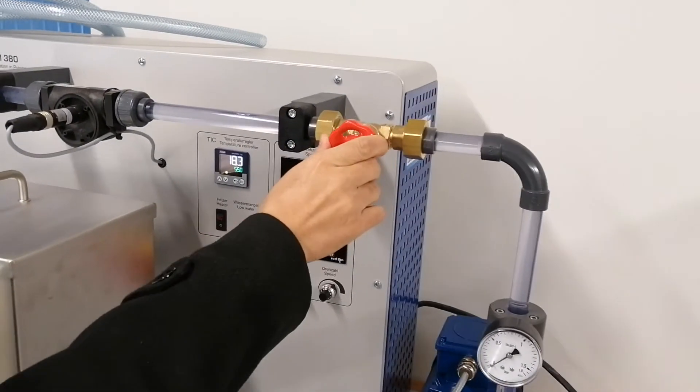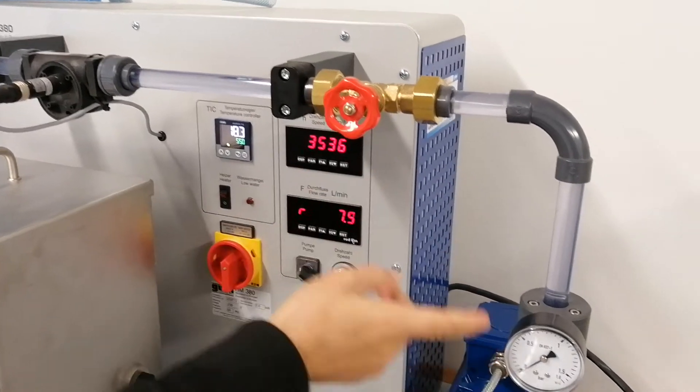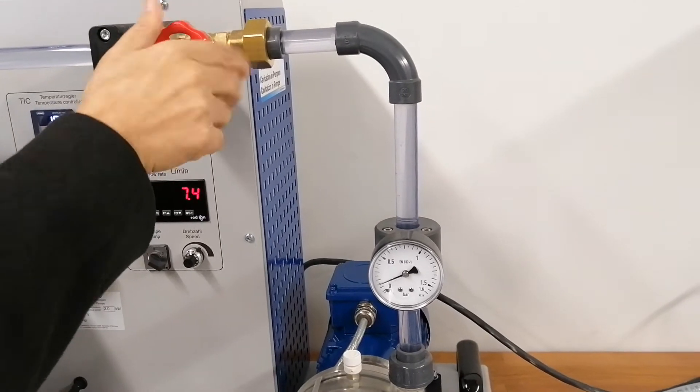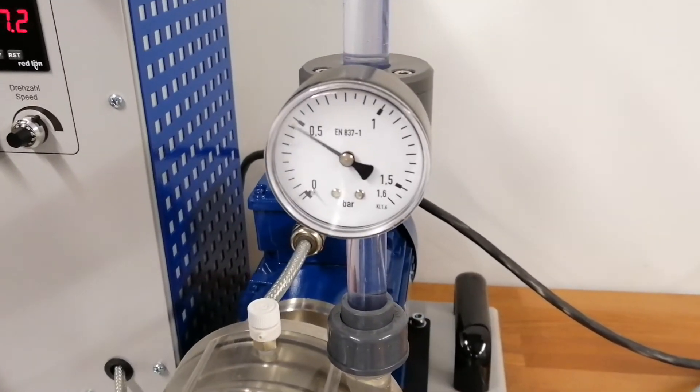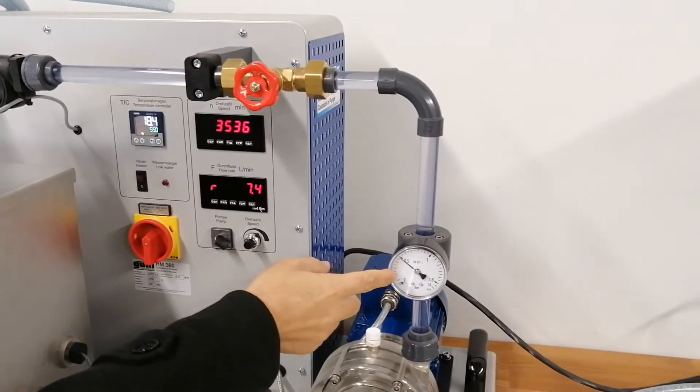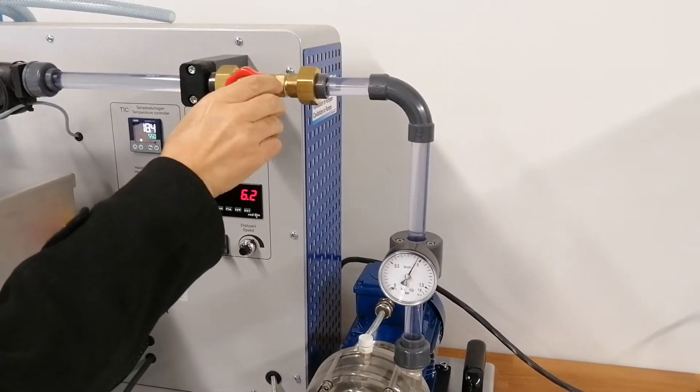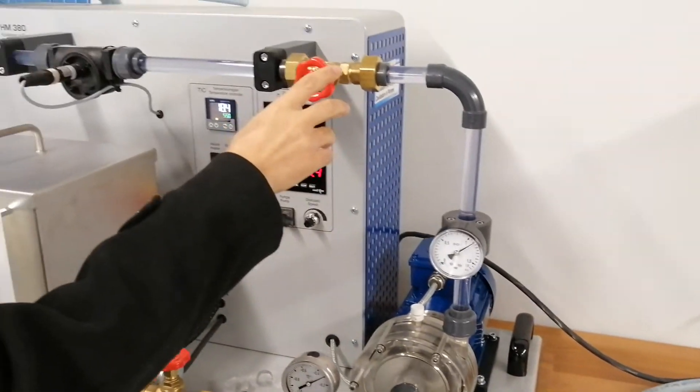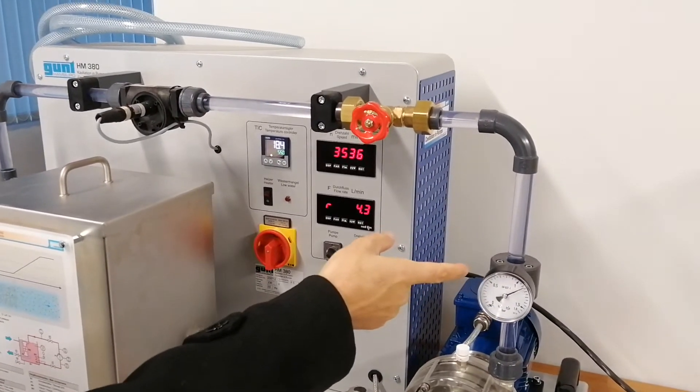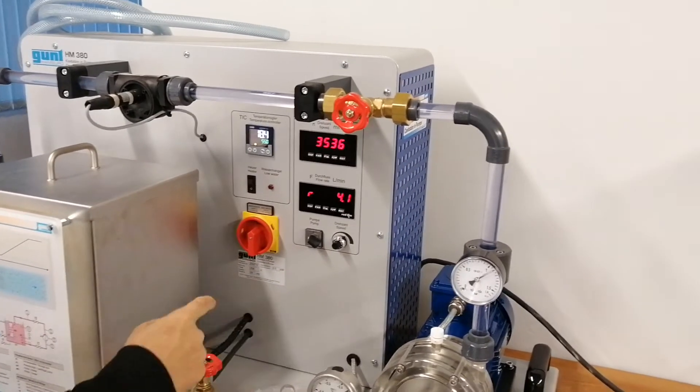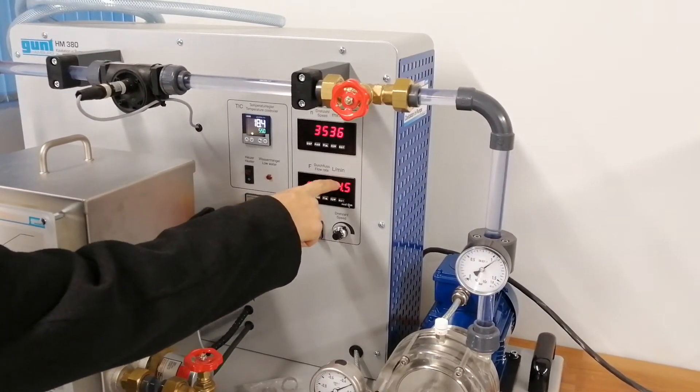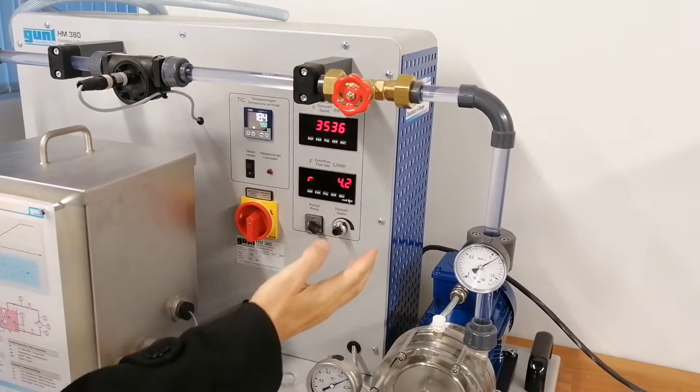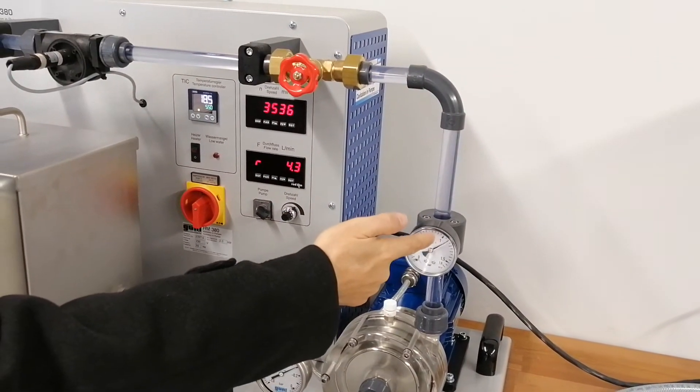Also, I want to show by closing this part, the pump head. Now, you can see, you can observe the pump head here. This is also in bar, this is the delivery bar. As you see, more than one bar. It means more than maybe 12 meters higher. It can move this liter per minute flow rate. This discharge can be pushed by this pressure now.